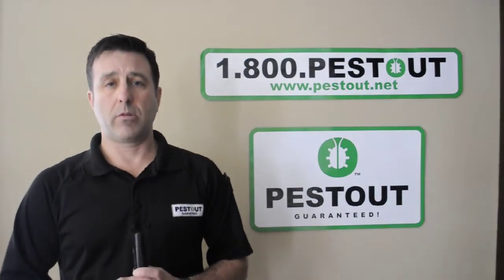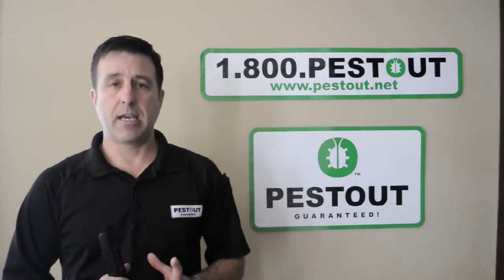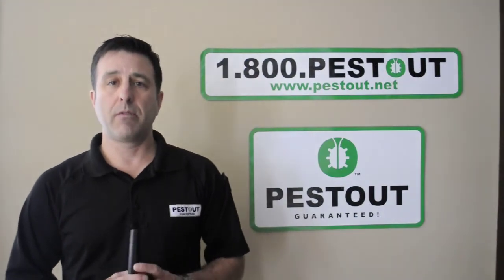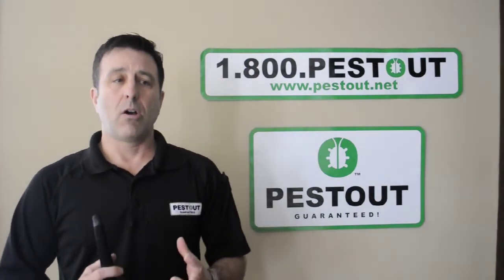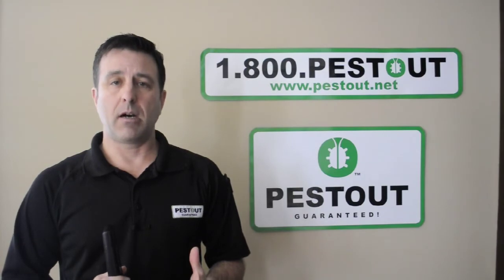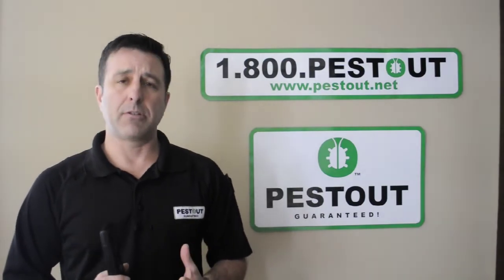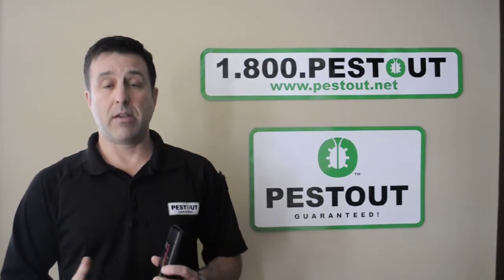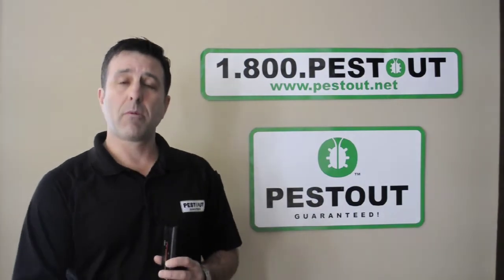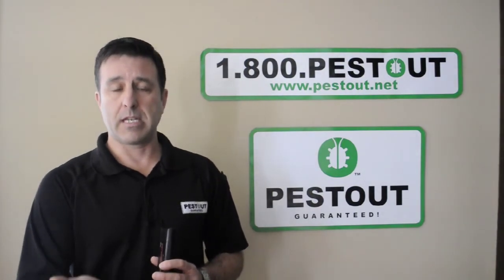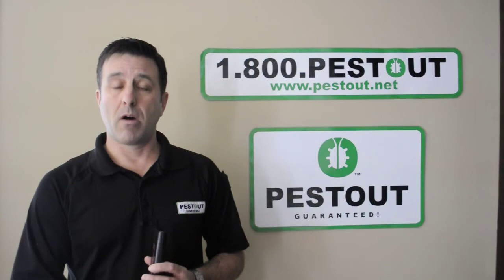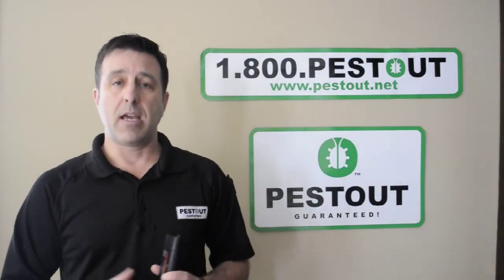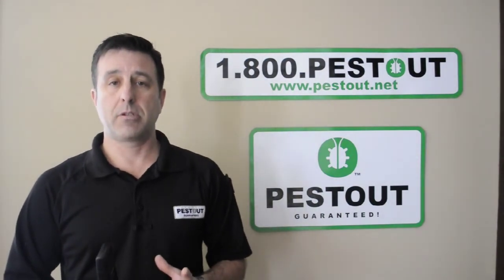So we look at the ductwork system. We don't do an air test, but we do a visual inspection, and there are some indicators that give us a key. If it's in the summertime, we'll actually feel the bottom of the fiberglass insulation, if it's filled with water, we know there's a real big problem that we need to address first.